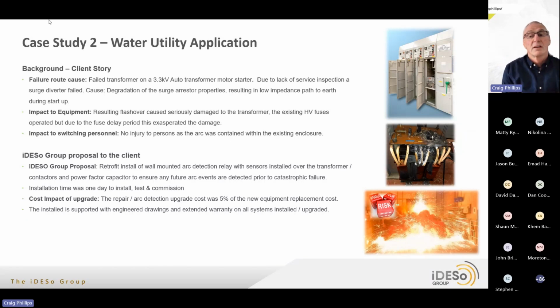The background story from the client was it had a failed transformer on a 3.3 kV auto transformer motor starter. If you look to the top right, there's a typical application of one of our systems, which would be a medium voltage motor starter system. And on this particular application, due to lack of service and inspections, the surge arrestor or surge diverter failed. The cause of that failure was the degradation of the surge arrestor, which happens.